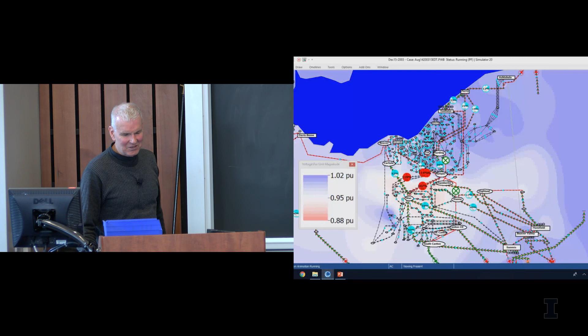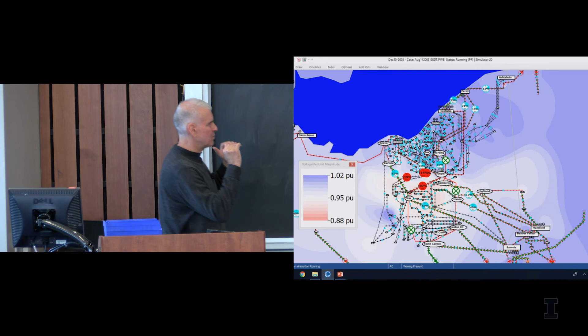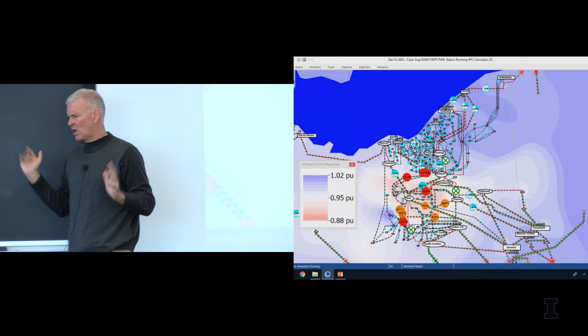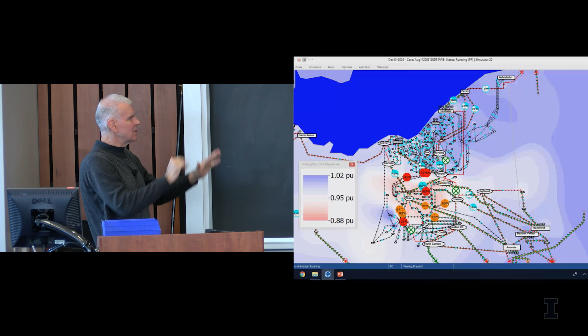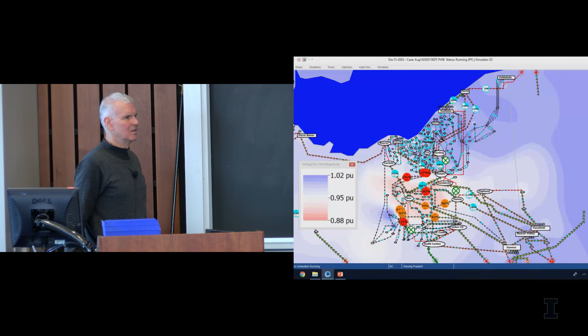The second one was also a tree contact. Then there was a third line that went out of service, again caused by a tree contact. And as that third line went out of service, we started to get even more lines heavily overloaded, and we moved into what we'd call a classical cascading blackout. Now some of the lines' protective relays started to trip them out of service. You started to lose load, and gradually over the course of the next half an hour, the grid got more and more stressed and eventually failed in a rather catastrophic way.